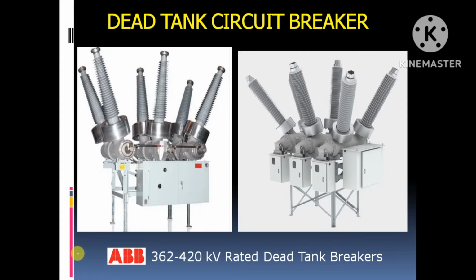This is an example of a dead tank circuit breaker. This is an ABB make 362 to 420 kV rated dead tank breaker. This is the tank, which is located at nearly ground potential. So this tank is located near ground potential, and that's why it requires more space and more gas. This is the interruption chamber. This is R phase, suppose Y phase, this is B phase. This is the interruption chamber, and it has bushings on the incoming side and the outgoing side.